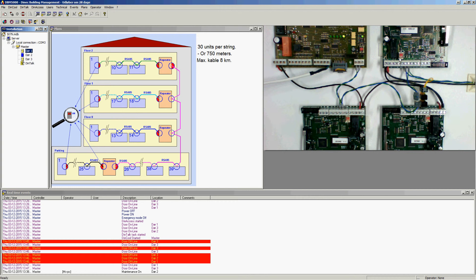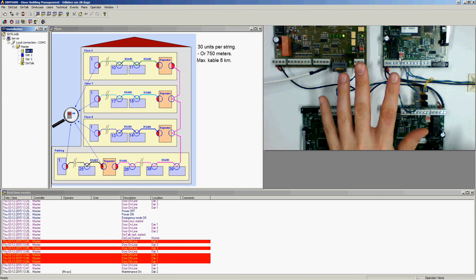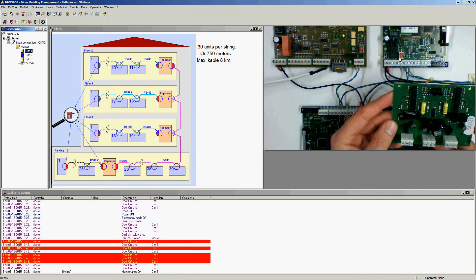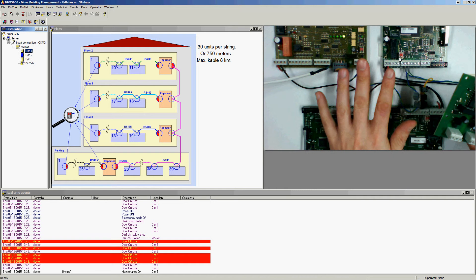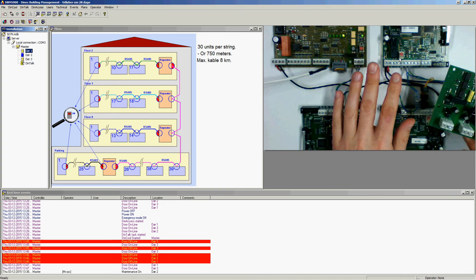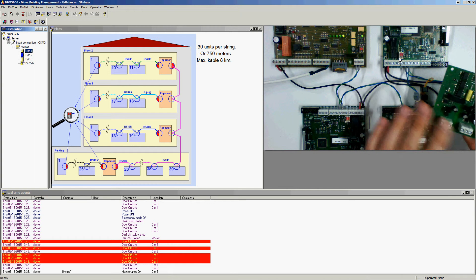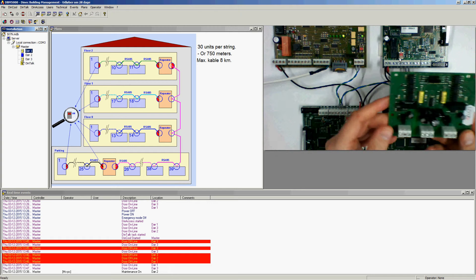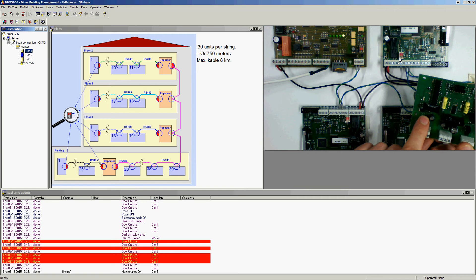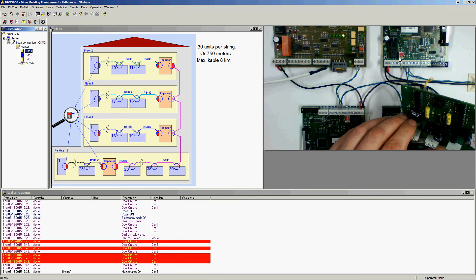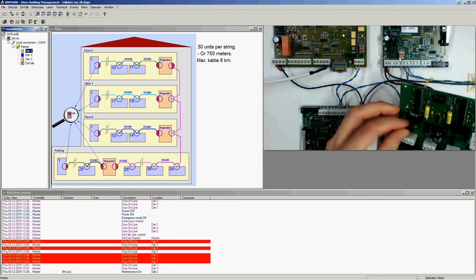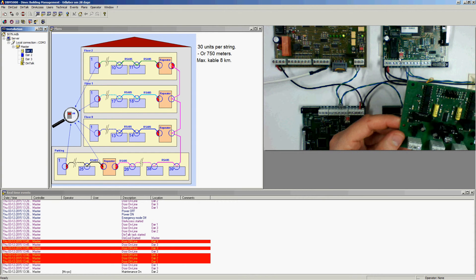If I have a number of doors and want to add a repeater — for instance going to another building, or if I have about 30 units or 750 meters — then I would need to add a repeater to start the new bus. I have to consider whether it is going to be terminated or not. These jumpers: if you take them off, you remove the termination; if you set them on, it is now terminated. So if this unit is not the last unit but instead the repeater ends the bus, I need to have the jumpers on the PCB.